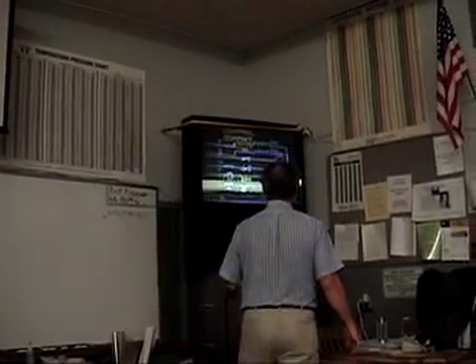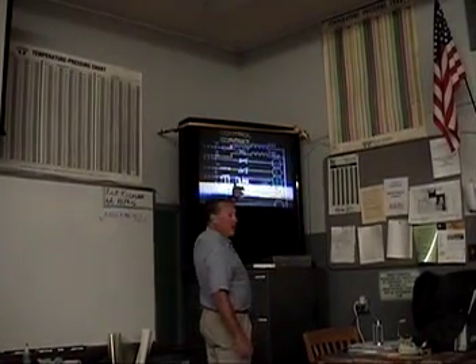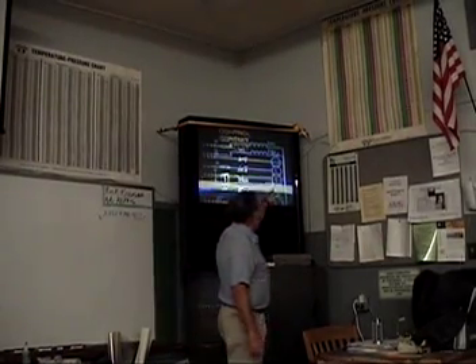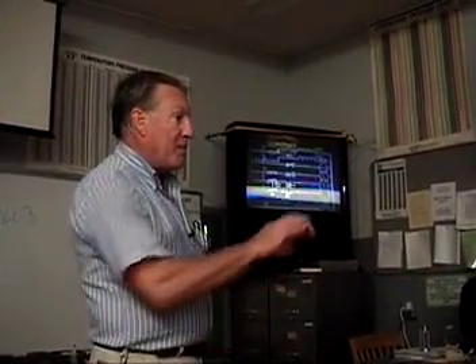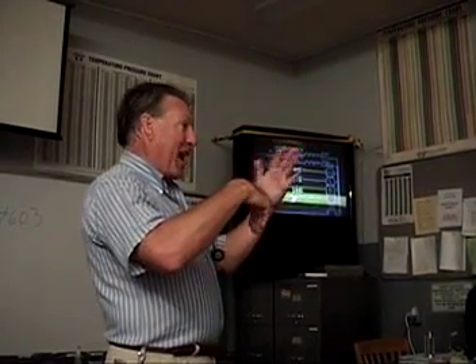Now, you guys seem to be getting a lot better at reading these schematics and following the electricity. I think doing it and then actually wiring it really helps. You can see on here, Y is going through a high pressure control and a low pressure control, and then going to your contactor coil. You all know Y turns on your contactor coil, right? So if your contactor coil isn't getting electricity, then you would go, well, power, path, and load. Do I have power? Yeah, I have power. Do I have power at the other end? No. It's the path, right? And if there's a low pressure and a high pressure control, it might be one of those. See, that's how you troubleshoot.